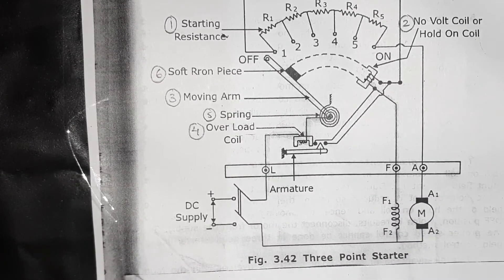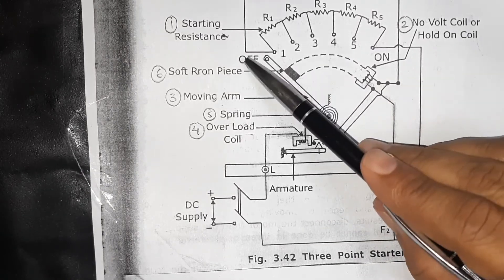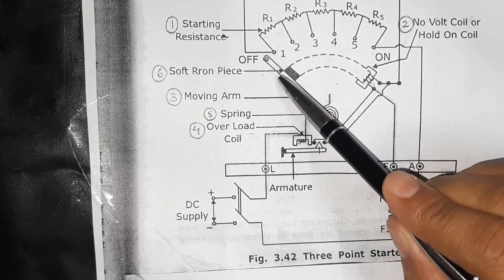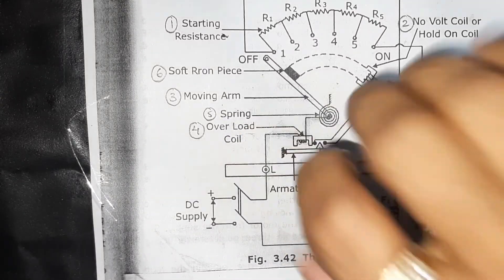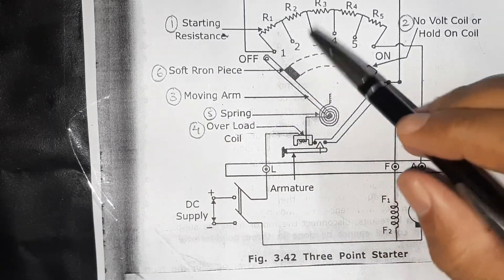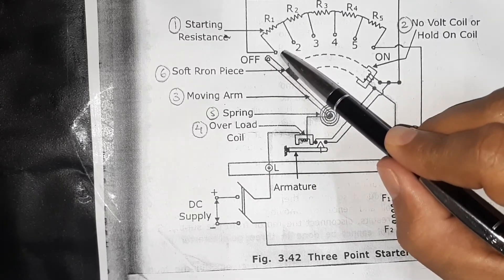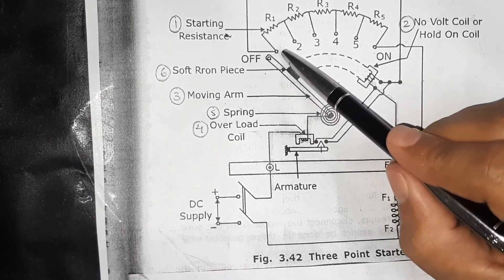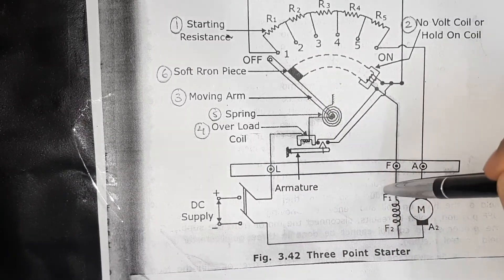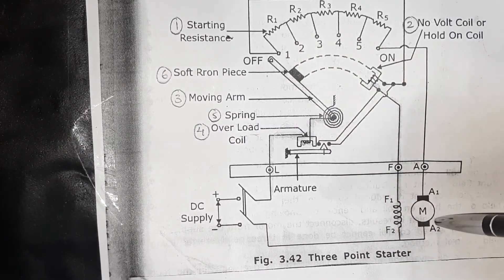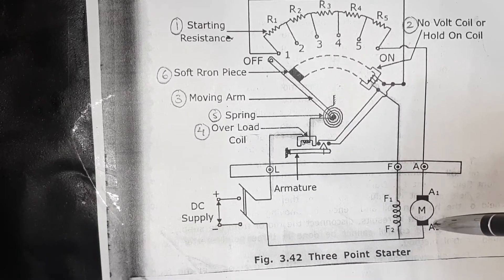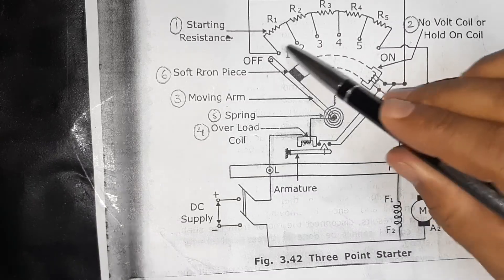Now let us understand the working of the three-point starter. First, keep the moving arm in the off position and switch on the supply. Then move the moving arm with the handle to the first stud. When the moving arm comes in contact with stud number one, the field winding is directly connected with the supply mains while the whole starting resistance is connected in series with the armature. So the starting current passing through the armature is limited by this starting resistance.